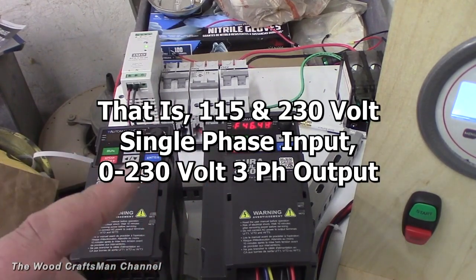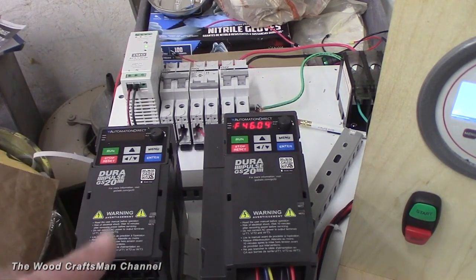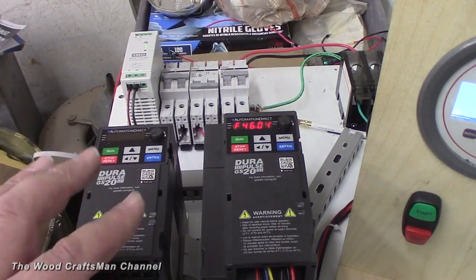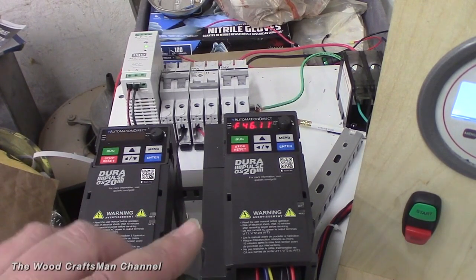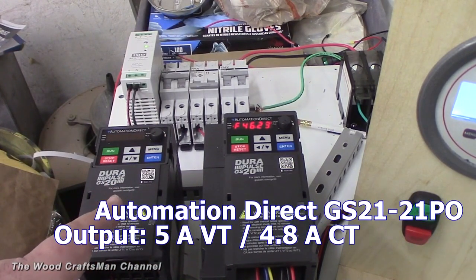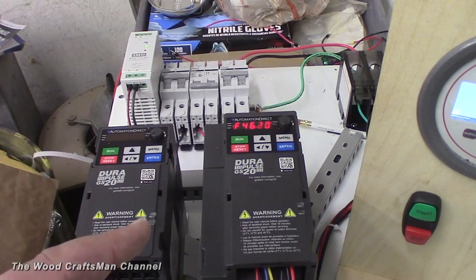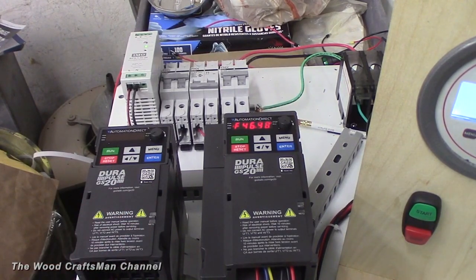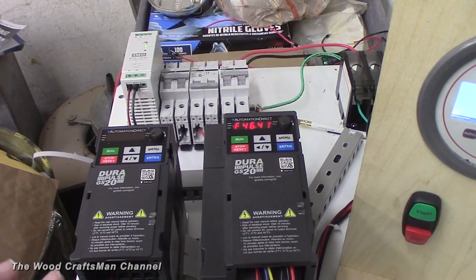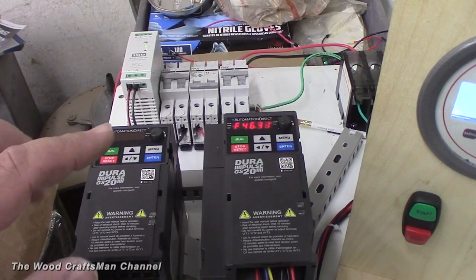One thing to point out about Automation Direct is they sell single-phase models and three-phase models. Single-phase goes up to three horsepower. If you need something bigger than three-horse, you have to go to a three-phase input and derate from there. These drives have full output capacity without derating — this one puts out 7.5 amps constant torque and 8.5 amps variable torque with 230 volts in.